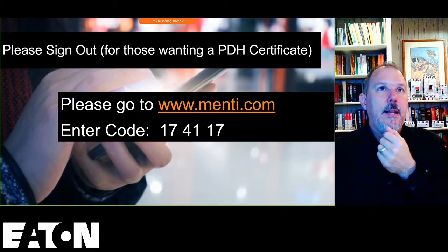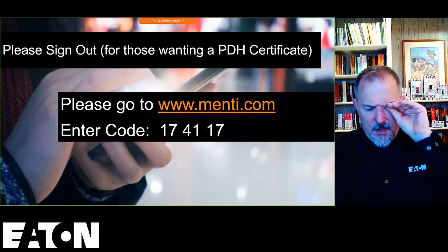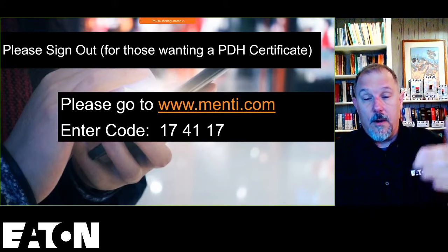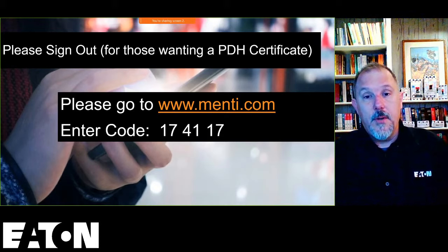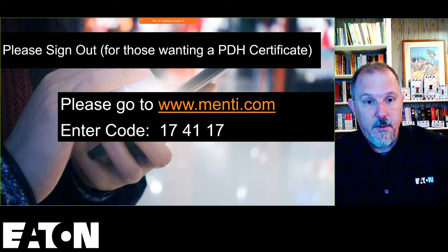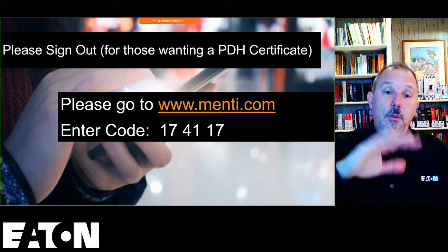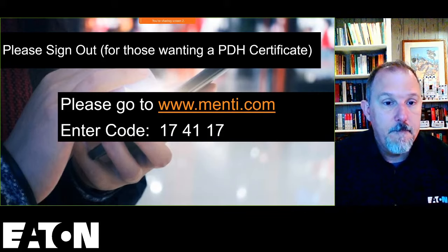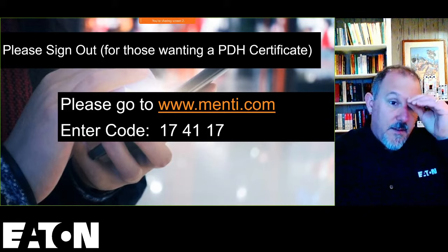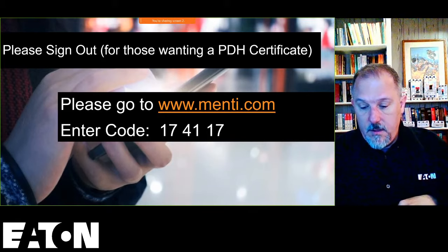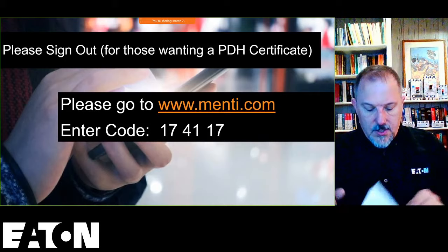That's good to know. And when you take a listed piece of equipment, to Ryan's point, they're putting the burden on the manufacturer to say, hey, just tell me what the minimum circuit ampacity and maximum overcurrent protective device is for this. You do the math, all that good stuff. Overcurrent protective device, 440.22. Let's take a look at what 440.22 says.